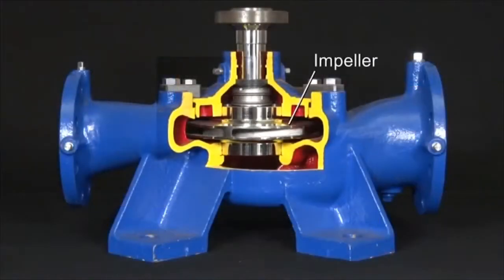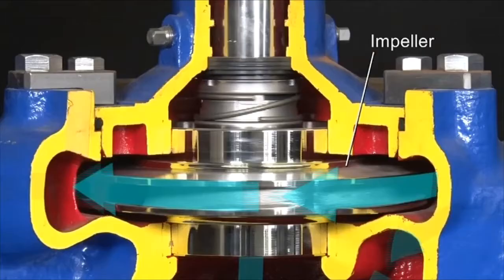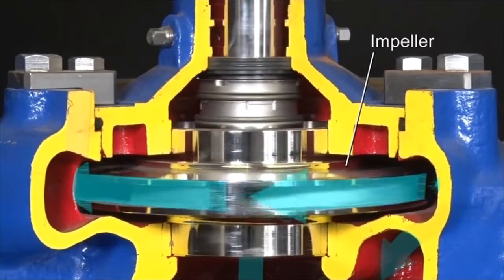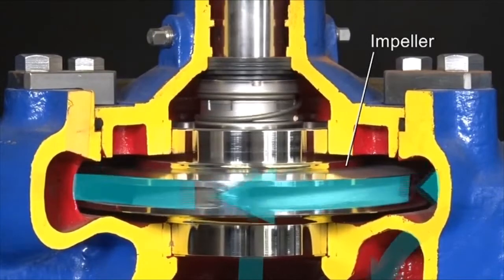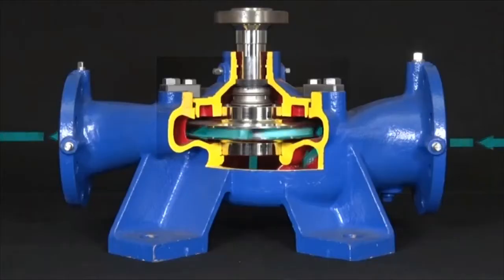Rotation of the impeller creates a vacuum at the center of the impeller, allowing the liquid to be drawn in through the pump inlet. Given pressure and velocity energy by centrifugal force, the liquid is pushed out through the outlet. Such repetition of suction and expulsion allows the liquid to be pumped.